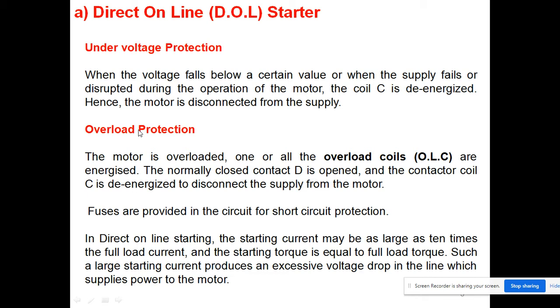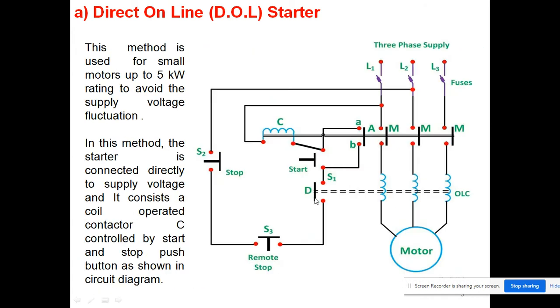If we have overcurrent, we will see here the overload protection. When the motor is overloaded, it means the coils which we are calling the overload coils are energized. In starting, the contact D was closed, but when these overload coils are energized, in this condition this will open, so you can see this will be open.